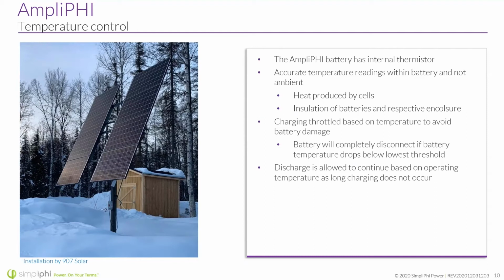Maybe it's -2 degrees outside, and maybe it's 20 degrees inside your enclosure, and then at the cells inside the battery, which is inside the enclosure, it's 40 degrees when it's charging - the battery takes in that temperature. So you have fewer false negatives, or false flags that say the battery's not able to charge because the ambient temperature is so low. That plays a big factor here. As far as the charging temperature goes, it's 32 to 120 degrees Fahrenheit.